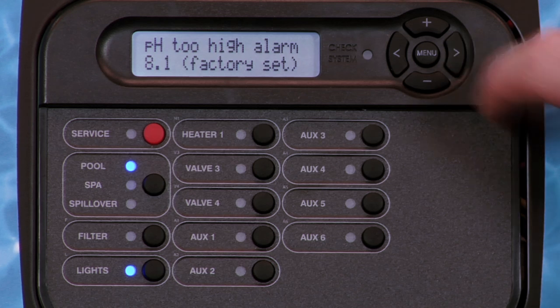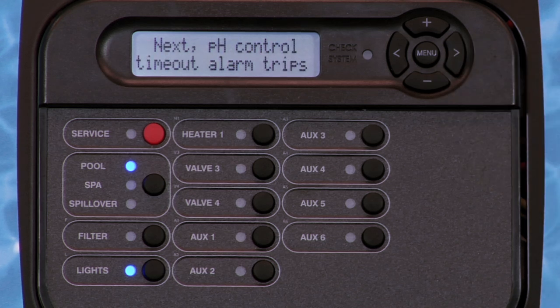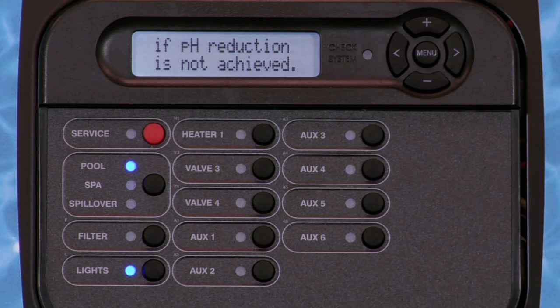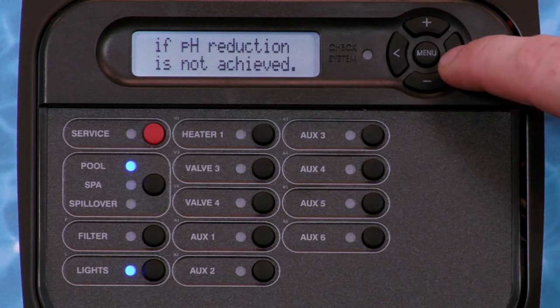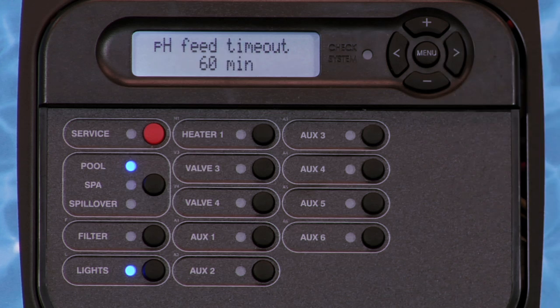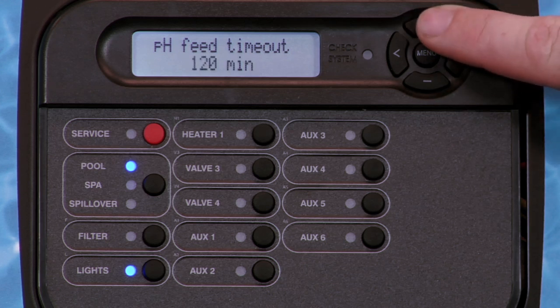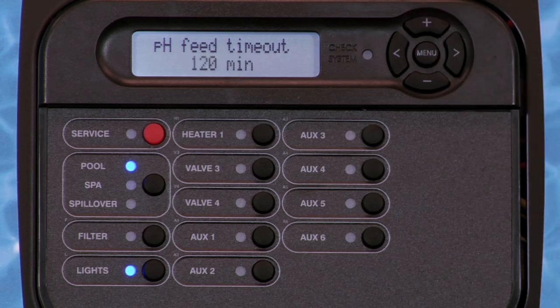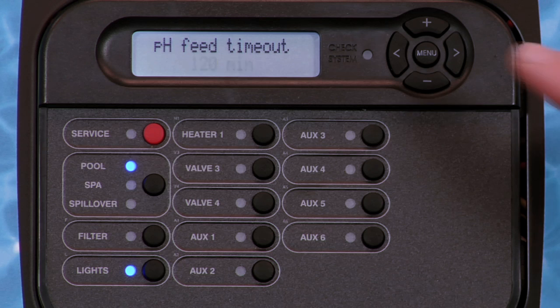Pressing the right arrow key twice will move through the next two screens, where the chemistry wizard explains the function of pH control timeout. The display will read, pH feed timeout, 60 minutes. This allows you to set the maximum amount of time that the pH reduction control will attempt to lower the pH level before an alarm is triggered. Pressing the plus or minus key will change the display from 60 minutes to 120 minutes. This may be needed for larger pools.